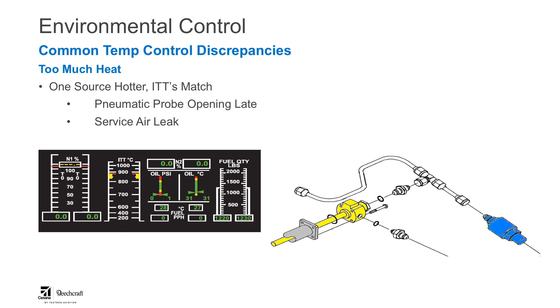So for a possible pre-cooler issue, we could look at maybe that pneumatic temperature probe is out of calibration, maybe it's opening late, and so it's causing things to run hotter. You could also have a service air leak that is either between the temperature probe and the modulating valve, or anywhere up to the temperature control valve. If we have a leak and we're not providing that service air when it's supposed to be provided, that too would cause it to run hot.